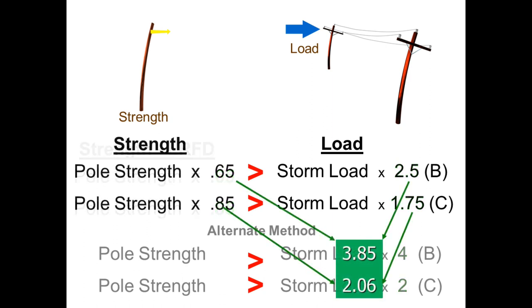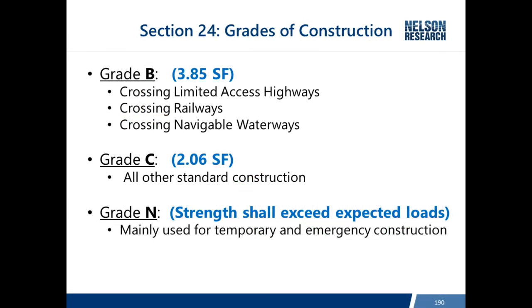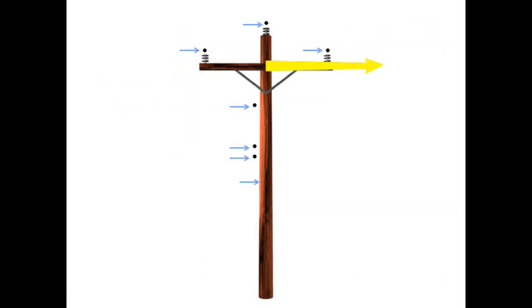Combining the strength factors and load factors gives a combined factor of 3.85 for Grade B and 2.06 for Grade C. When the format was changed to LRFD, these factors were chosen to equate to past practice — so poles are still almost four times stronger in Grade B and two times stronger in Grade C. Grade B is required for crossings of limited-access highways, railways, and navigable waterways, while Grade C covers the majority of distribution construction.